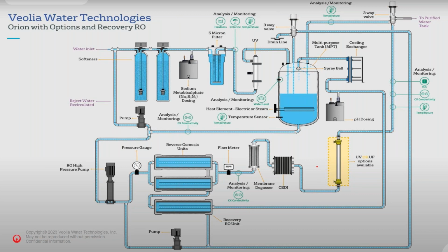Now this system can be hot water sanitized, so periodically you can hot water sanitize, and as I say, there's a heating medium in here, it could be electrical or steam, generally steam for larger units. We have a temperature sensor on the bottom of the tank here, a temperature sensor on the outlet here, and we also have a temperature sensor on the return line here. So this heats the water up to above 80 degrees.